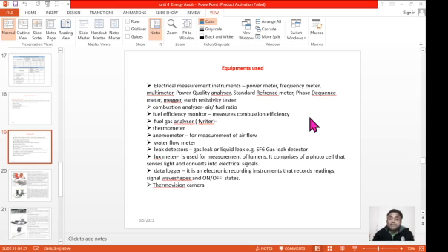The hot spot is defined as the temperature of 50 degrees centigrade, beyond which it is highly risky to go with that hotspot. So we have to attend that hotspot by taking outage or hotline work and tighten it or replace it as required. And then we have to see that the temperature comes down below 50 degrees centigrade.